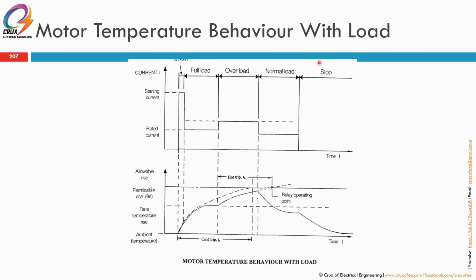Okay, this is the behavior of the winding temperature, motor temperature, with load. So during starting, high current, 6 times to 8 times, it only starts to increase the temperature. At full load, it will increase to a certain value, but it will stabilize. At full load, once it's overloaded, it will keep on increasing. If the overloaded condition is not removed, it will continue to increase until the hot trip temperature setting.